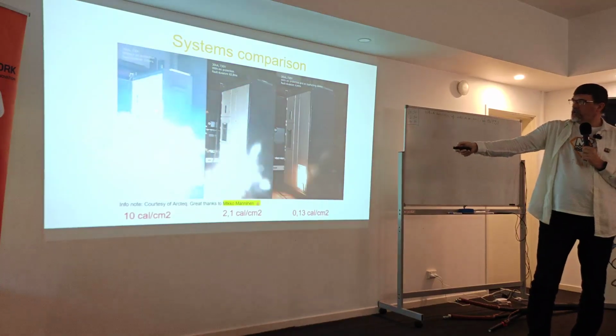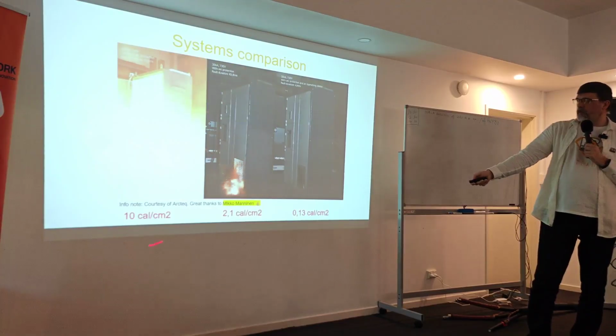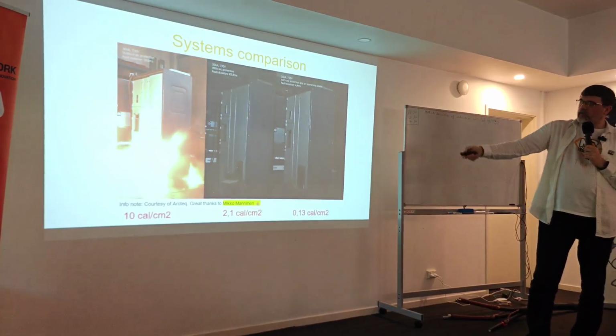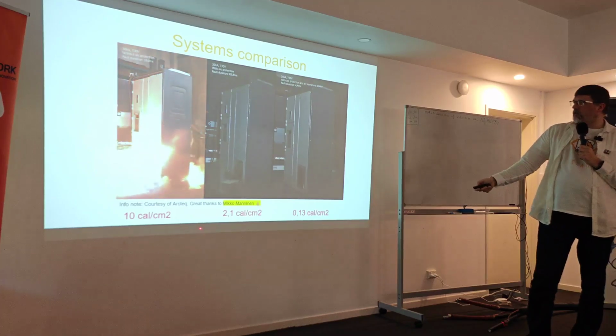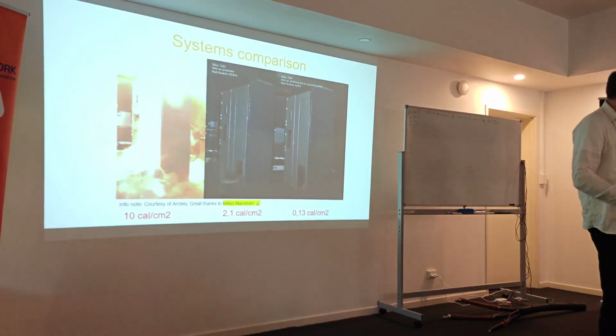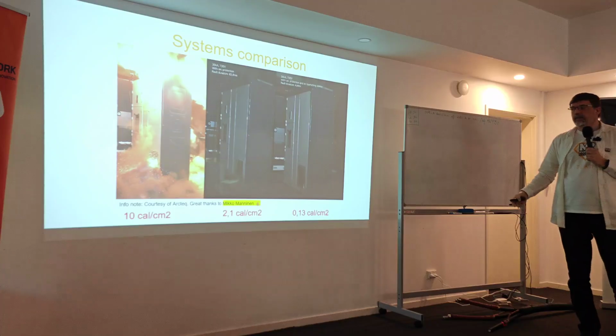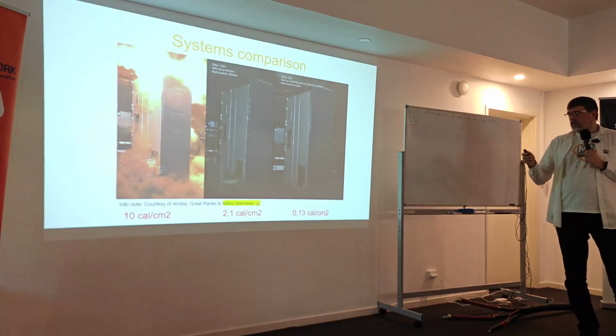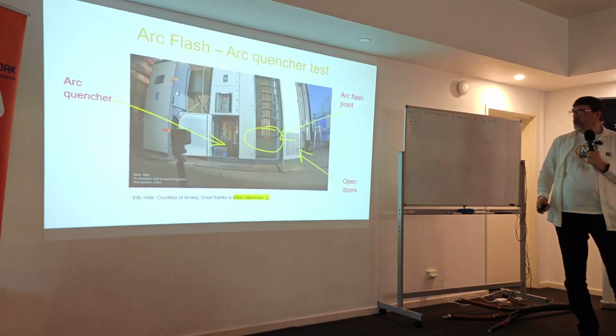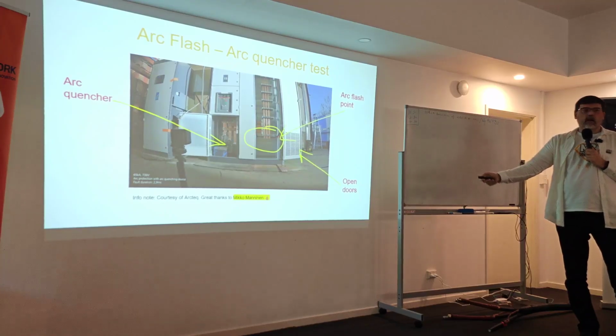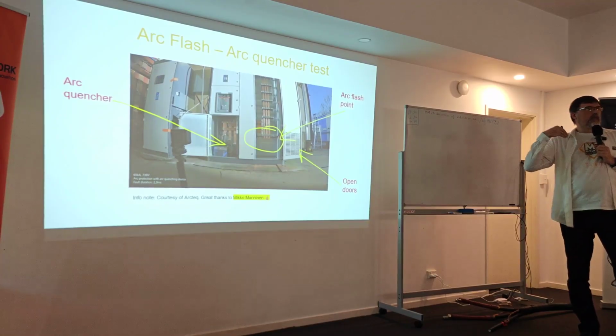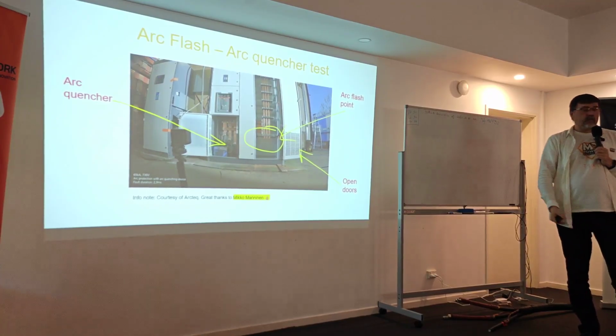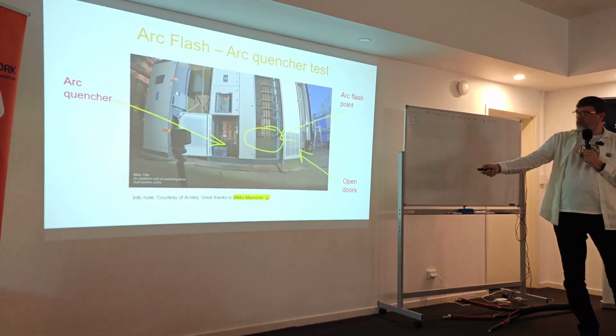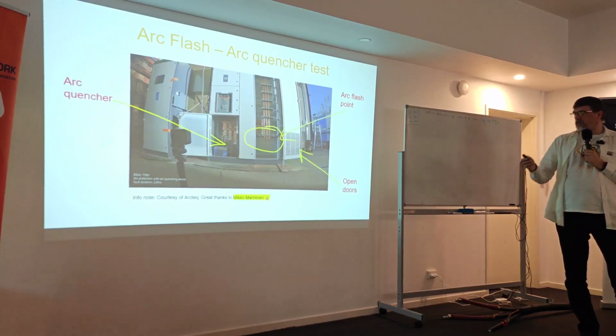This is the video, the same video that David showed you. What I calculated is how much energy it is. So 300 milliseconds in this case was 10 calories because it was 30 kiloamps. This was 2.1, and with the quencher it was 0.1. Pretty much, that's the difference. So you can see this, but the goal behind it is to reduce the energy. This is a nice test that Miko sent me when they did it with the doors open. So what you do, normally you just put a wire on the bus bars and try to initiate the arc. And the quencher is here, built in. So it has to short circuit those buses and kill the arc, and then send a signal to the breaker.